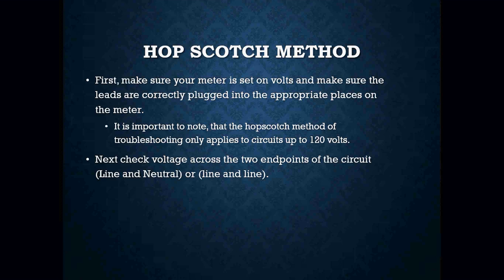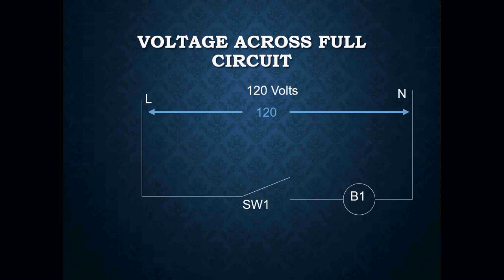The first thing that you want to do when you are using the hopscotch method is make sure that your meter is set to volts and that the leads are correctly plugged in to the appropriate places on the meter. It is important to note that the hopscotch method of troubleshooting only applies to circuits up to 120 volts. Now, what you're going to do is check for voltage across the two endpoints of the circuit, your line and neutral. Okay, so here we are. The beginning part of doing the hopscotch method is you have to make sure that you do indeed have voltage to your circuit. So you're going to go across L1 and neutral. In this case, 120 volts is being read.